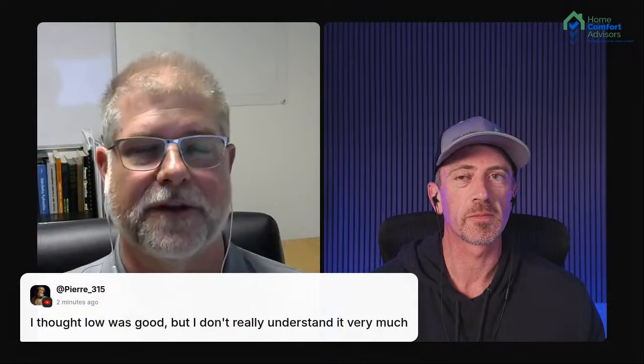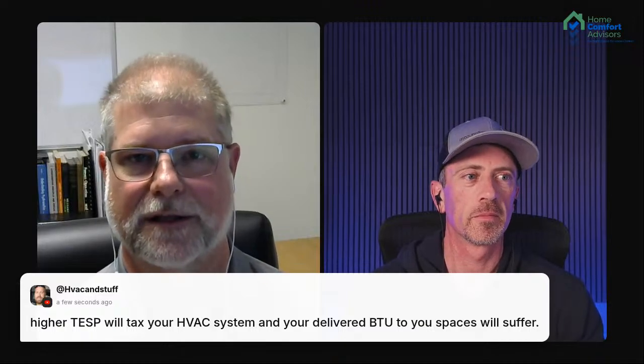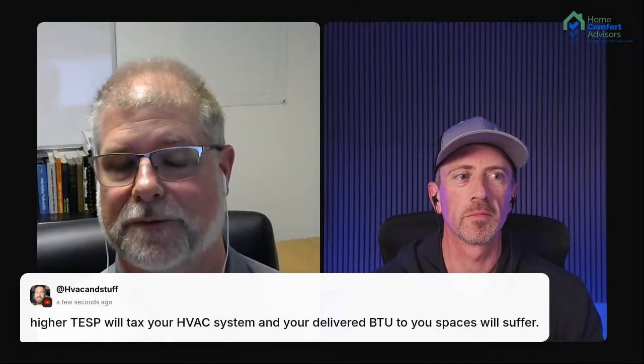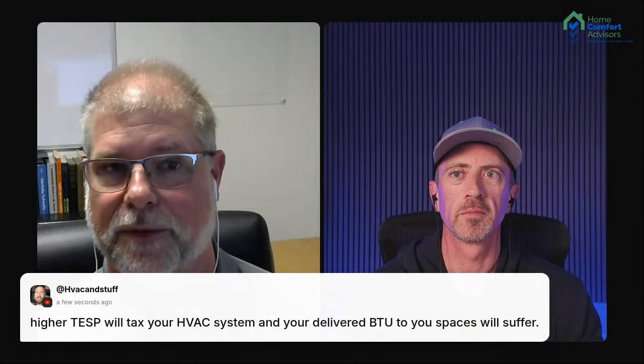It is if the ducts are tight, and that's one of the things about low static pressure, it can fool you. If the ducts are tight and the system is clean and airflow set right, then yes, it could be a good thing. But it could also be an indication that the blower is dirty. It could also be a sign that you've got disconnected ducts that have fallen apart. So once again, that's like a lot of the things that we've talked about. It does depend. There are situations that you could have low static pressure that are great, and you could have it where it's low and it may not be good at all, depending on the installation and system condition.